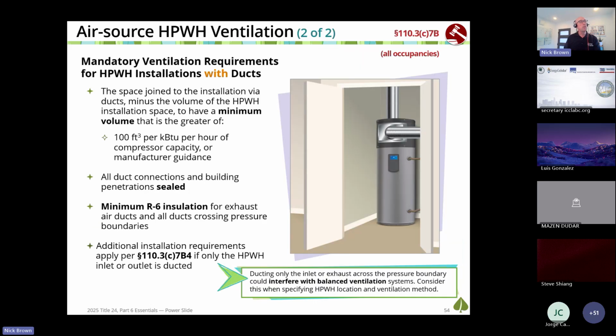The last option, ducting. We can get them to, in effect, be in a large enough room if we duct the small room to a neighboring room or outside. Okay. All duct connections and penetrations need to be sealed, with minimum R6 insulation on those ducts. And there are additional requirements if they're ducting only one of the inlet and the outlet.